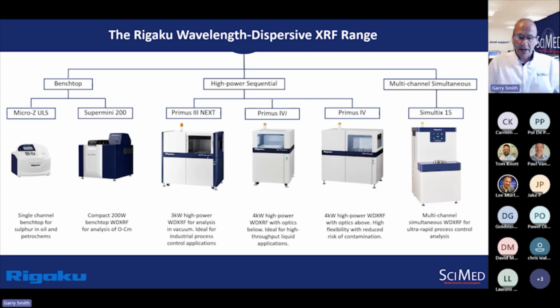The Primus 4 is the sister spectrometer to the Primus 4i, 4 kilowatt with the same functionality as the Primus 4i, but optics above. So that brings in the improved benefits of optics above, such as reduced risk of sample contamination from sample spillages. And finally, we have the Simultix 15, which is a large multi-channel simultaneous system, which is ideal for situations where we need ultra rapid process control. So it's a very high throughput environment where sample testing turnaround time is very, very important, and this will measure multiple elements simultaneously with WDXRF configuration.